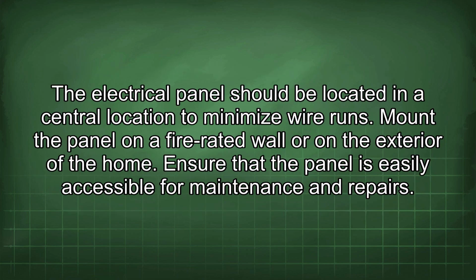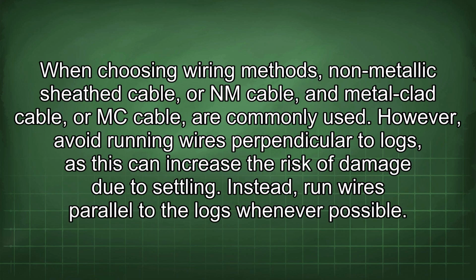The electrical panel should be located in a central location to minimize wire runs. Mount the panel on a fire-rated wall or on the exterior of the home. Ensure that the panel is easily accessible for maintenance and repairs. When choosing wiring methods, non-metallic sheath cable or NM cable and metal-clad cable or MC cable are commonly used. However, avoid running wires perpendicular to logs, as this can increase the risk of damage due to settling. Instead, run wires parallel to the logs whenever possible.